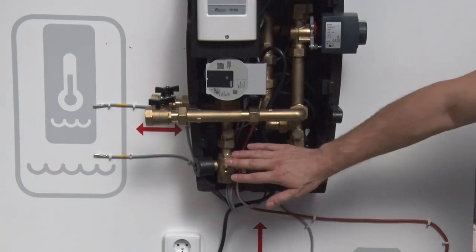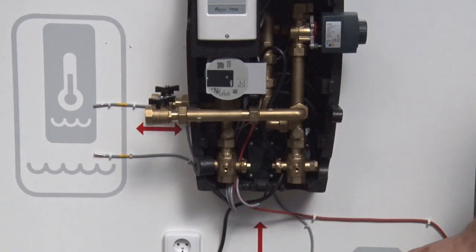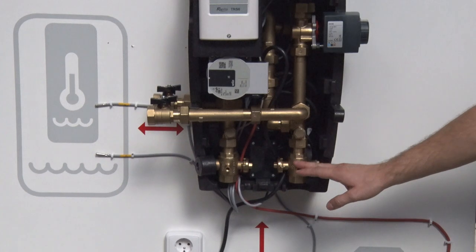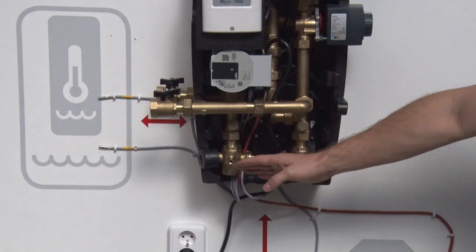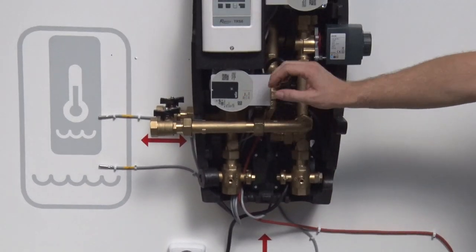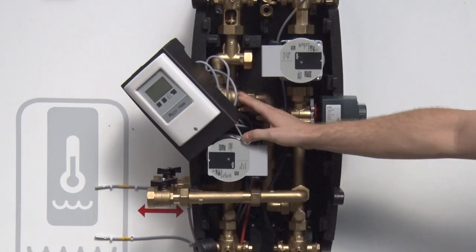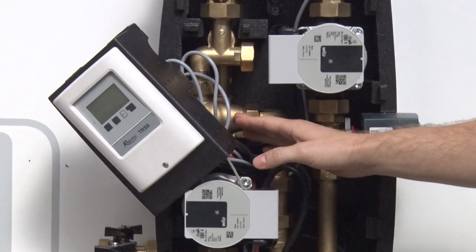Its bottom part involves ball valves to connect a boiler. On the right side there is the boiler flow pipe, and on the left side the boiler return pipe with a circulation pump and a load valve keeping the temperature at 55 degrees.